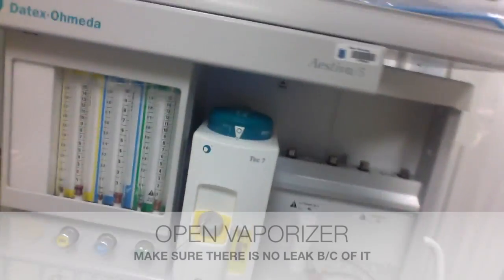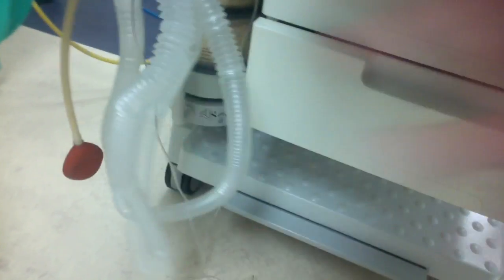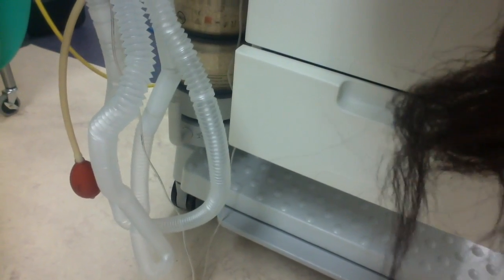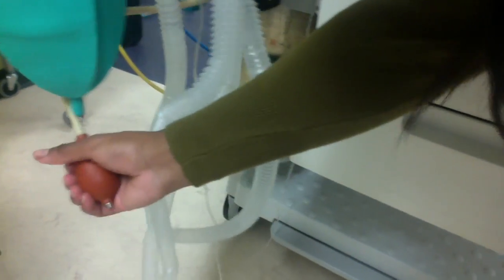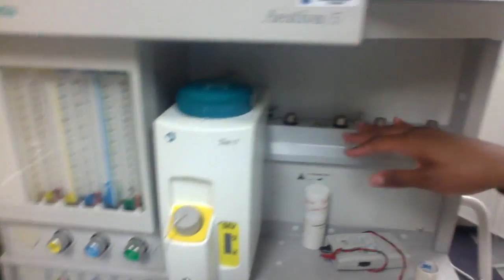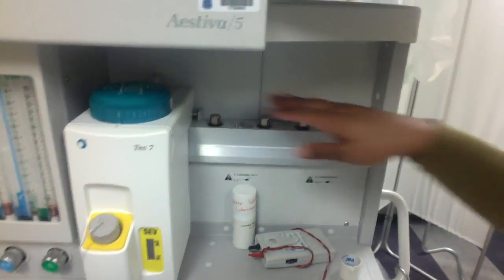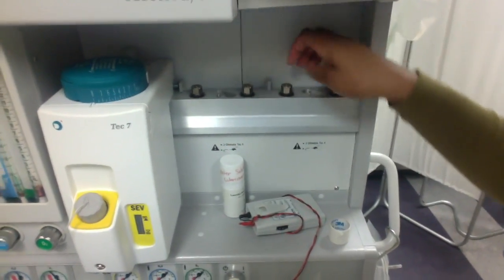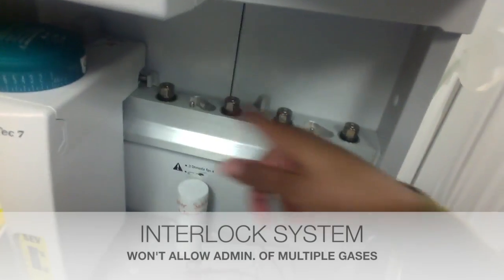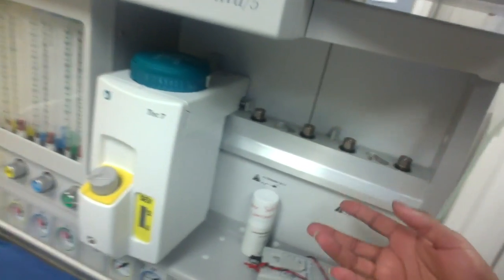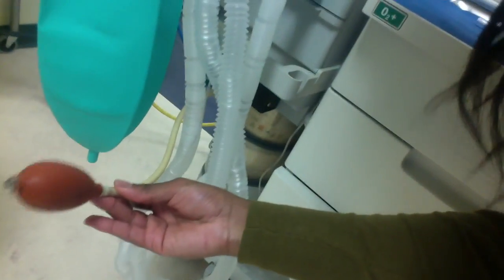And then what I'll do is try and open up a vaporizer. This bulb should inflate once I open that vaporizer. There we go. So then I'd deflate that again, and that should hold for 10 seconds. And while that is holding, if there were other vaporizers here, I would try and open these as well. And they should not let me because of what is called an interlock system. With one open already, no more should be able to open so that I can't deliver a combination of gases. So I do that with each vaporizer, and again, testing this and making sure that it occludes for 10 seconds.